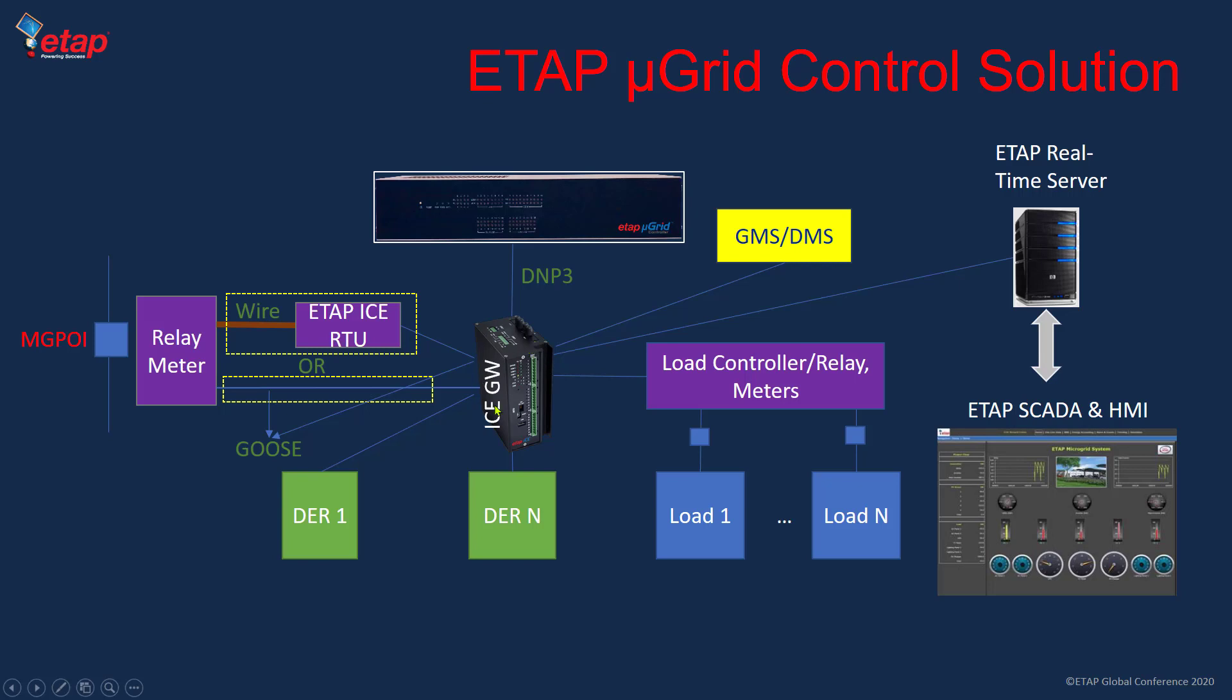One of the roles of the gateway is that when dealing with a microgrid, we're dealing with different assets that may communicate with different protocols. The gateway is able to communicate with different protocols, 61850, DNP3, Modbus, and all other common protocols. It even has hardware connections, analog inputs or digital inputs and outputs, and converts everything to a unified protocol.